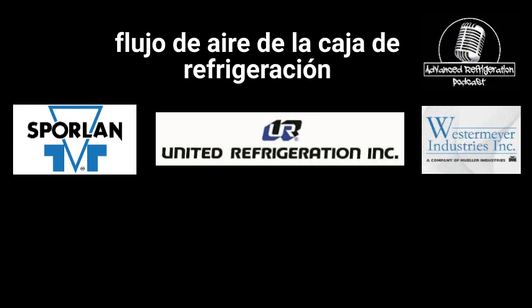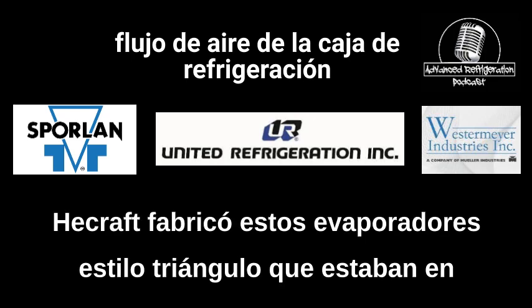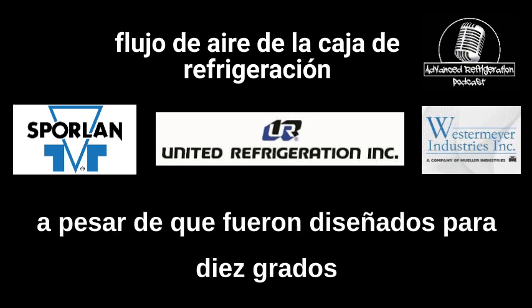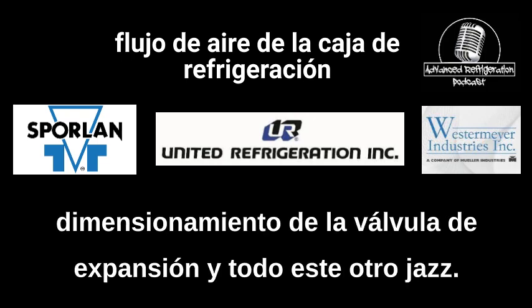So, well, we had a problem. Heatcraft made these triangle style evaporators that were in one of a major chain, and they had a beacon system in there, and these things would run, even though they were designed for a 10-degree TD, they were running 15, which messed up the expansion valve sizing and all this other jazz.